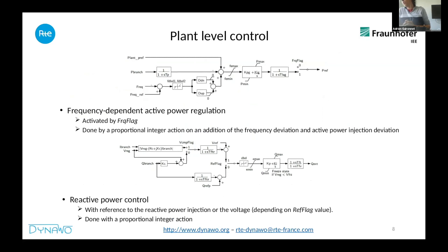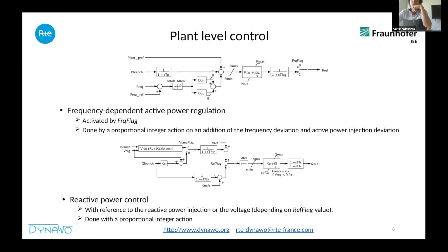Looking in more detail inside the plant-level control, you have an active power track — a channel — which is the frequency-dependent active power regulation that could be activated or deactivated. It is basically a proportional-integral controller on the frequency deviation. You have the frequency and its reference, going through some limiters and then into the proportional-integral path. There is a flag that enables activating or deactivating this path. For reactive power control, it is quite the same — also a proportional-integral that could be configured — and it is based on reactive power injection or voltage, depending on the type of control you want.